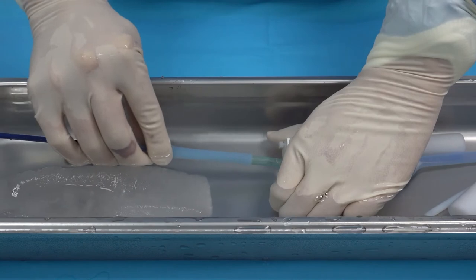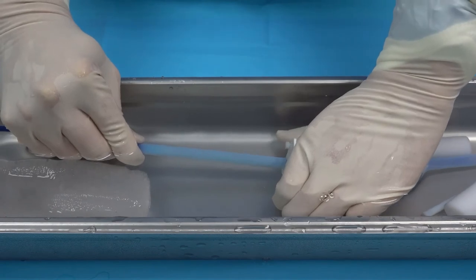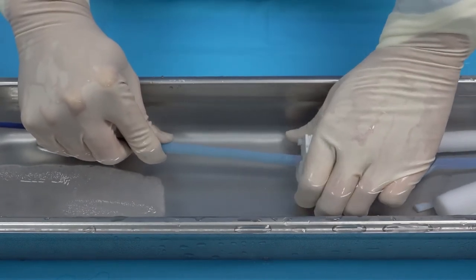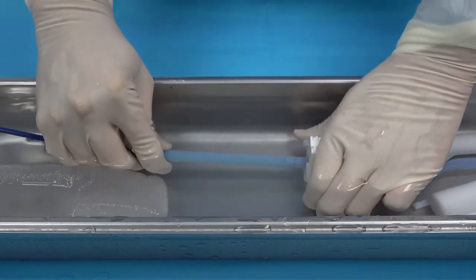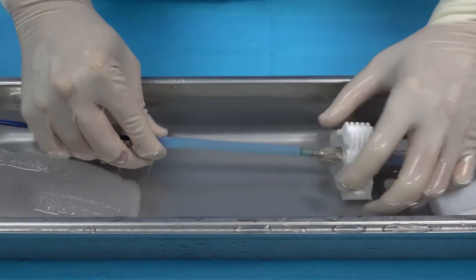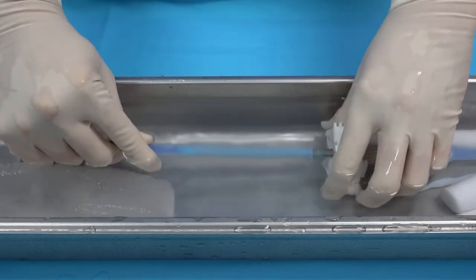Then advance the loading tube to catch the inflow end frame. Move the crimper more distally, followed by crimping, and push the loading tube forward. Maintain the crimping and the loading tube forward force while asking the assistant to rotate the micro knob anti-clockwise to advance the capsule tube and catch the inflow end frame. Withdraw the loading tube and rotate the delivery system to check whether all the inflow end frame is captured inside the capsule.